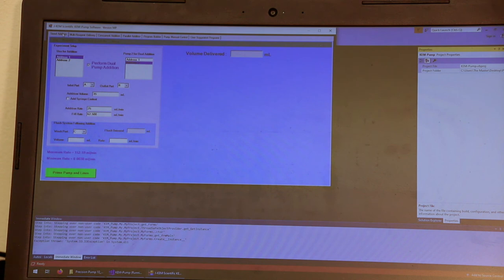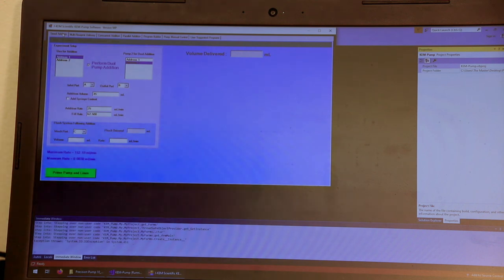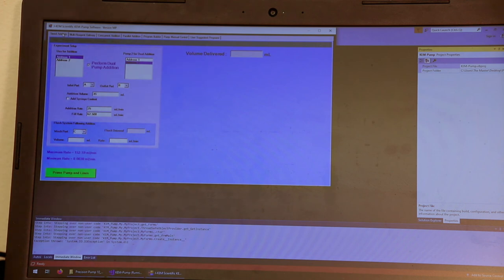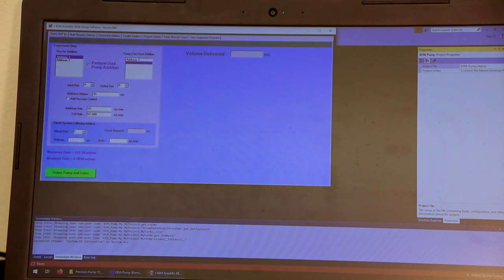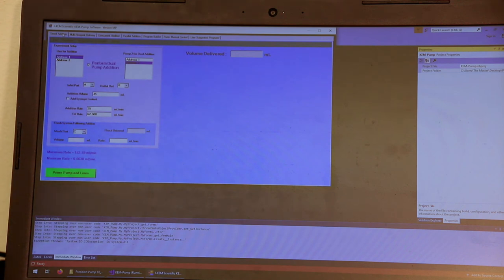Now what you can do with it is say, well, I'm running my reaction, but my reaction needs to be run at a very specific pH. You could enter, I want you to maintain that reaction, for example, at a pH of 5.2. So, the reagent you would put on the pump at that point, for example, is acid. If your reaction produces base, then the reaction would run itself. The pump would continuously monitor the pH of the solution and it would add small increments of acid to maintain the pH at exactly the pH that you requested.